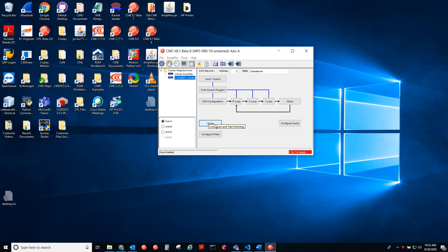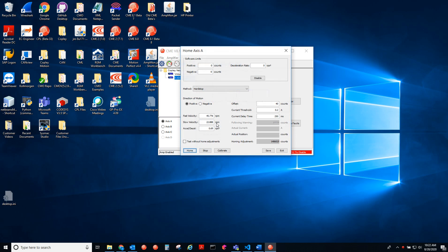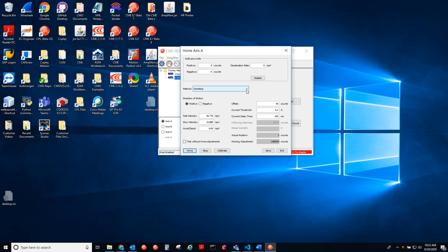So we go to the homing tab here to test the homing routine. Here we have some software limits. Those do not take effect until after the motor has been homed, after the homing has been referenced. Here we have a list of all of the homing routines that you can test.